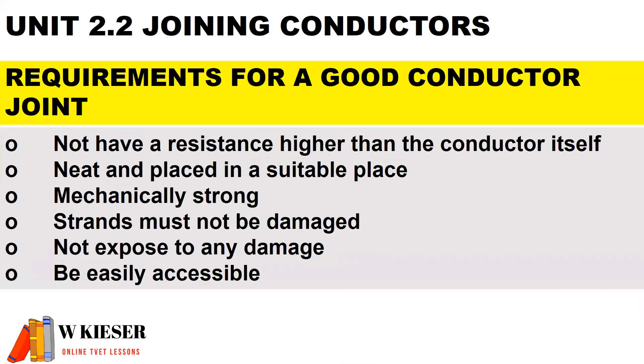The requirements for a good conductor joint: the joint should not have a higher resistance than the cable itself. It should be neat and placed in a suitable place, mechanically strong, strands must not be damaged, not exposed to any damage, and should be easily accessible.